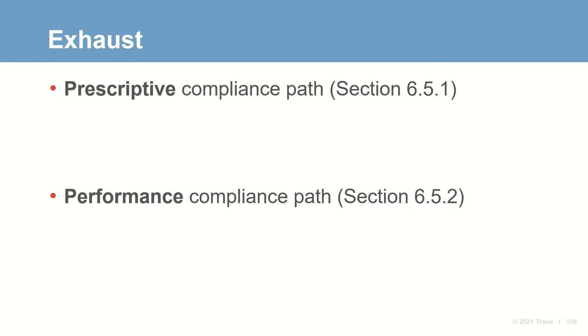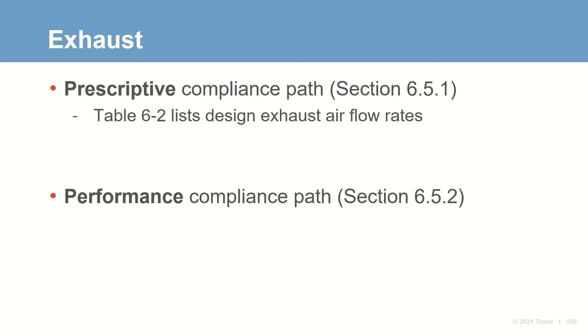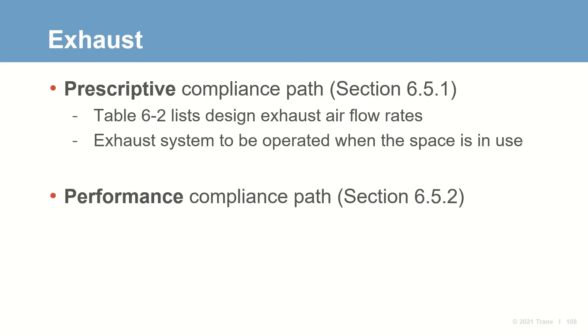This section includes two compliance paths: a prescriptive path and a performance path. When using the prescriptive path, you simply look up the required exhaust air flow rates in a table, similar to the ventilation rate procedure. The exhaust system is then to be operated at this rate whenever the space is in use.